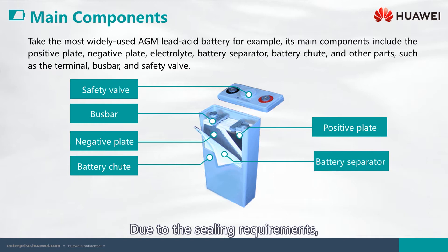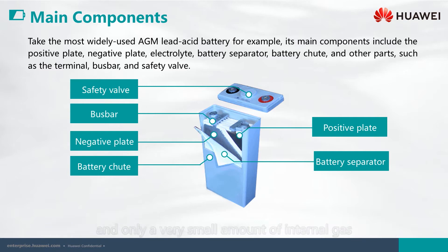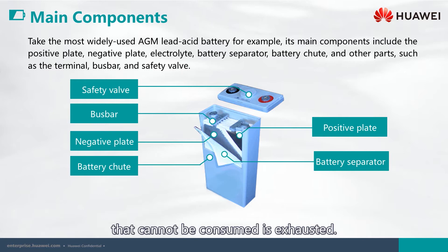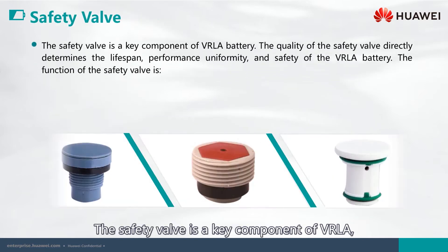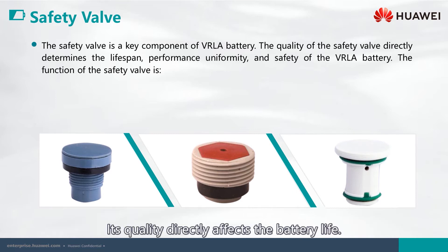Due to the sealing requirements, the VRLA battery cannot generate much gas during charging, and only a very small amount of internal gas that cannot be consumed is exhausted. The safety valve is a key component of VRLA, which prevents the internal pressure from growing too high. Its quality directly affects the battery life.